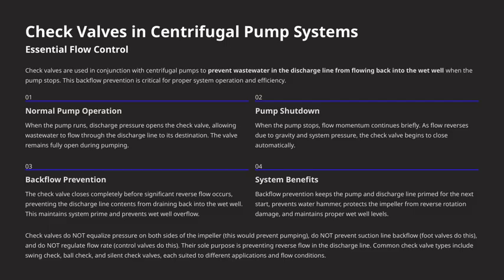There are several benefits to this setup. Backflow prevention keeps the pump and discharge line primed for the next start, which is crucial for quick, efficient operation. It also prevents water hammer, which can cause damage, and protects the impeller from reverse rotation, which could be damaging. Plus, it helps maintain proper levels in the wet well.